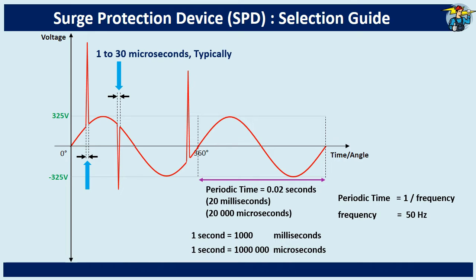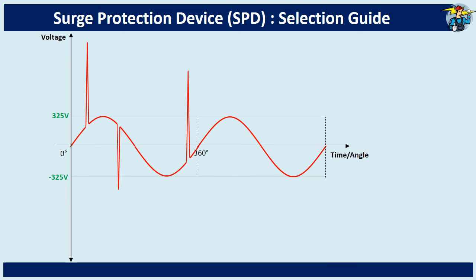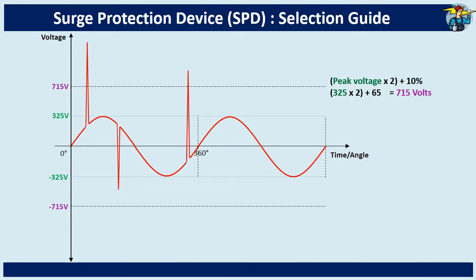Most of these surges originate through lightning strikes or electrical switching of inductive loads. When continuous operation of an electronic system is required, it is essential to limit these peaks below the impulse immunity of the equipment. If we don't know the impulse voltage it withstands, simply take twice of the maximum voltage plus another 10%, as the safe value. So, 715 volts is the safe range for electronic equipment here, and spikes within this range can be considered as harmless to critical equipment.